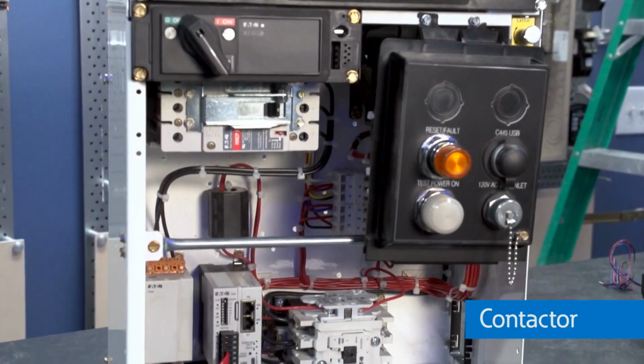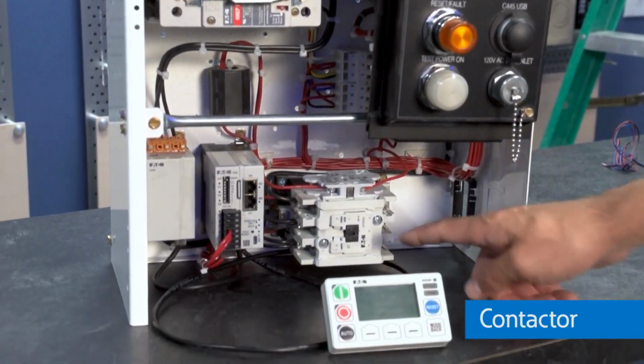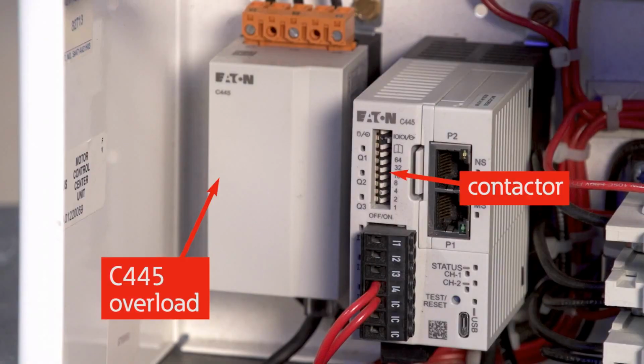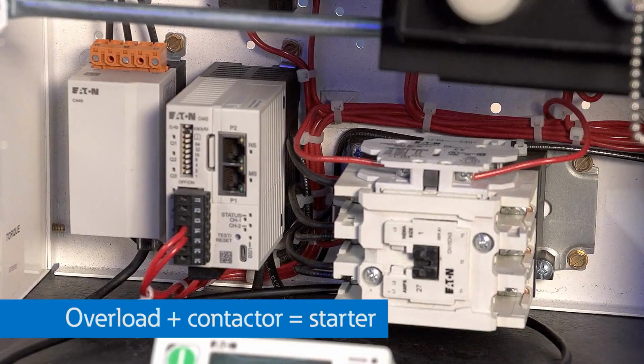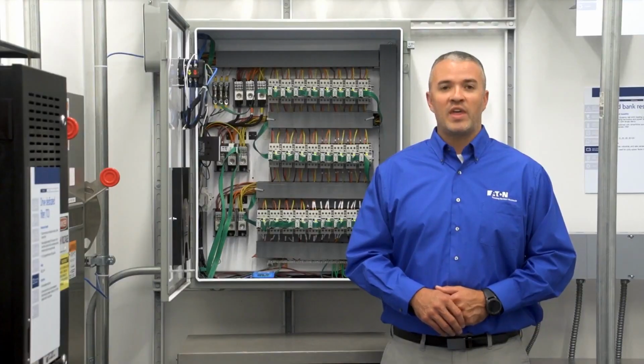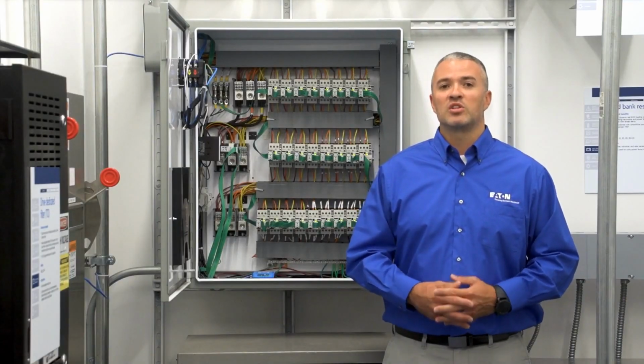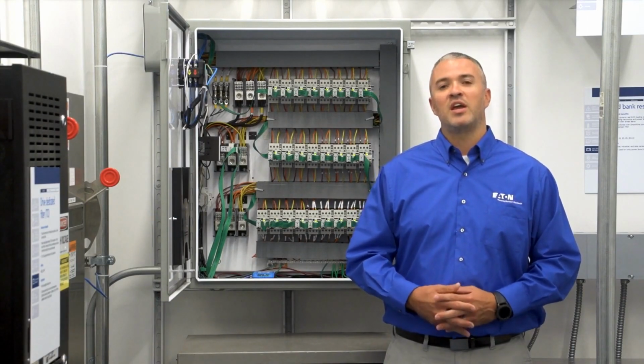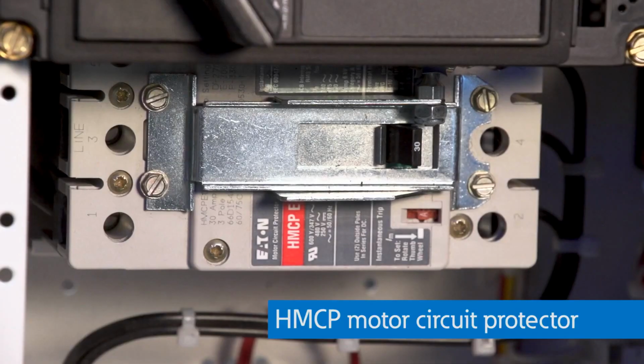What is the difference between a starter and a contactor? This can tend to be confusing because a starter is simply a contactor with an overload relay connected to it for motor protection. This motor control center bucket shows a contactor with this overload protection, which as a system will be considered a low voltage motor starter. Without fault protection, this motor starter could be damaged if it attempted to interrupt fault current, so we include this HMCP to provide fault current protection in an MCC bucket.